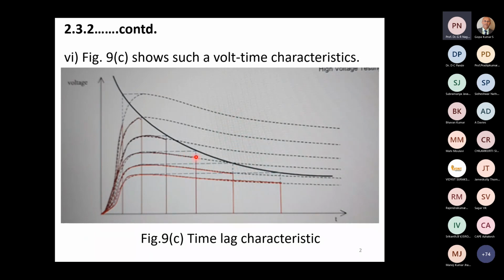This is the time to flashover, and this is the peak voltage. I increase the voltage further - this is the peak value, and time to flashover is reduced, so I get this point. If I increase it further, I get this voltage and this time to flashover. So this curve is known as the voltage time to flashover characteristic.